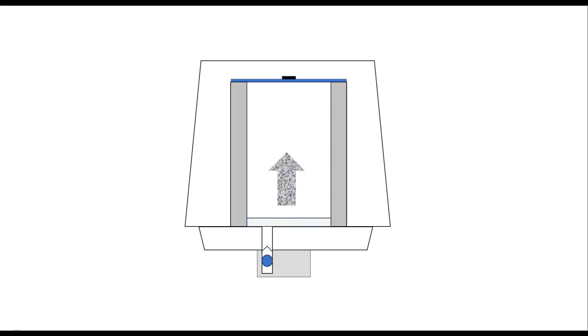When oil mist enters the filter, it is pushed through the filter medium to the outside. The filter medium cleans the air and the air then escapes and goes into the atmosphere. As the oil mist goes through the medium, oil droplets are left behind. These oil droplets then fill the basin at the bottom of the oil mist filter.